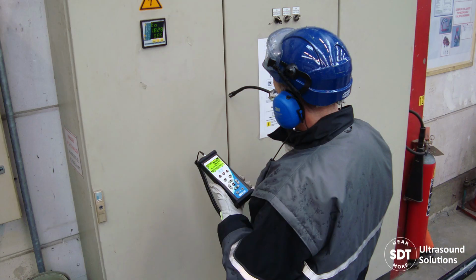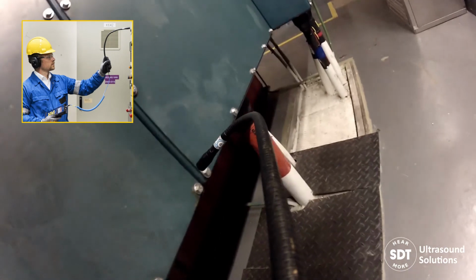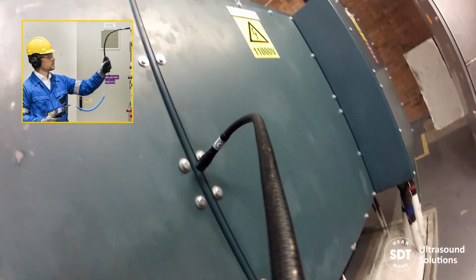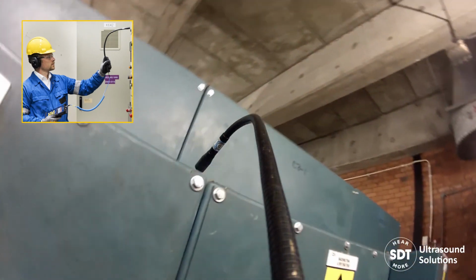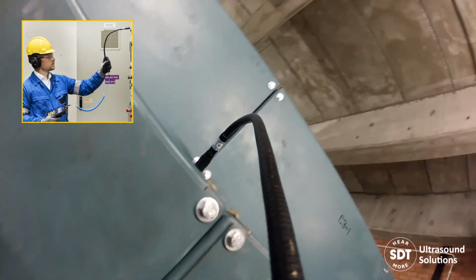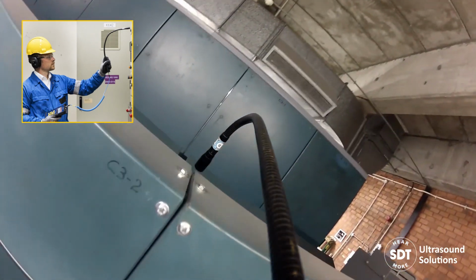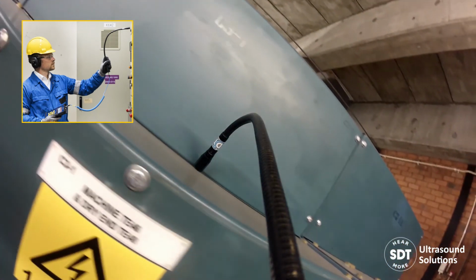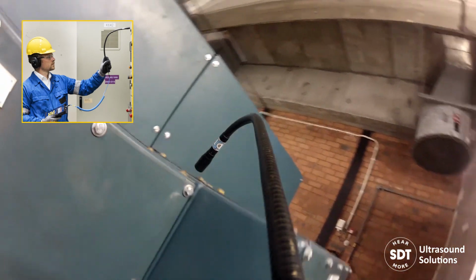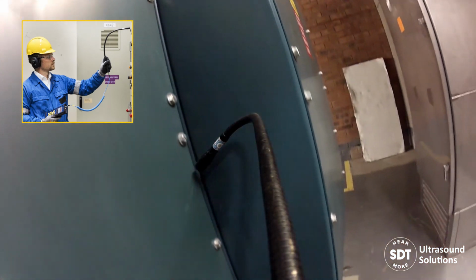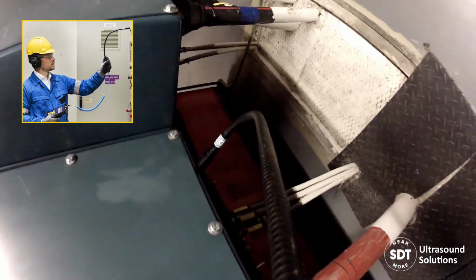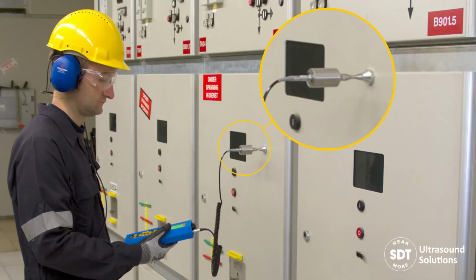How great is it to inspect motor circuit control panels without opening them up and exposing technicians to risk? An air gap is all that's required for ultrasound inspectors to pick up partial discharge activity inside the panels. Air gaps can be around the panel doors or through the cooling vents. In the event that a panel is hermetically sealed, simply place a magnetic mount ultrasound sensor on the outside of the panel and listen directly through the steel cabinet.